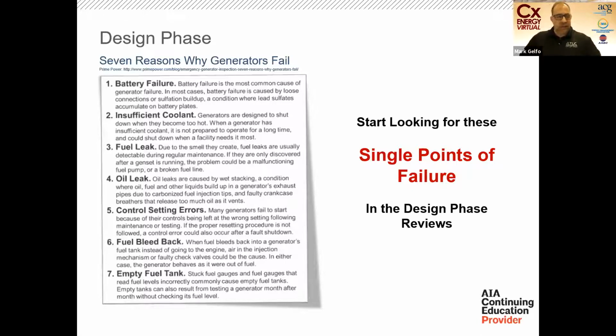You can see this list the good people at Prime Power put together of some common issues: the fuel tank was empty, which always cracks me up—that we didn't have fuel in the generator. But most of these are preventable: battery issues, insufficient cooling, fuel leaks, oil leaks, control problems, and fuel issues. These are usually maintenance and operation issues.